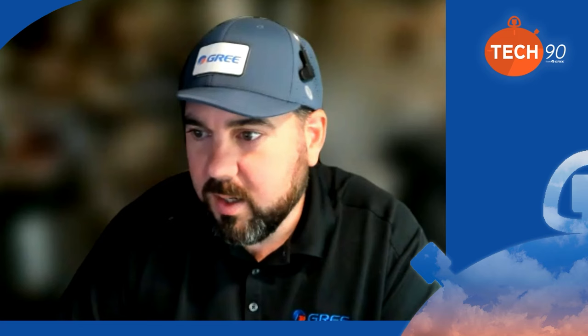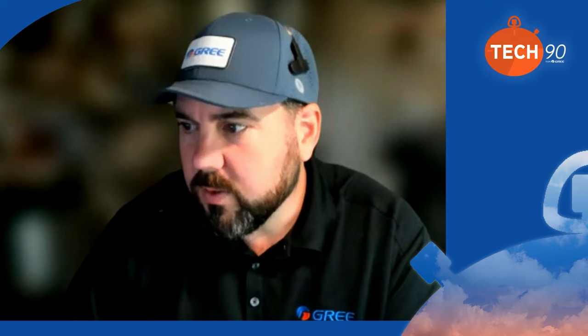David says, curious of the failure rates for the Flex rotary compressor as they run very hot. What do you think, Greg? First of all, I want to say we don't have a large compressor failure rate. I'm not going to say we don't have compressor failures, but I was just pulling the numbers on that this week, looking at warranty numbers on compressors. It's very, very low. It's less than 1%. That's excellent news. I didn't even know that. Just a little tidbit there.